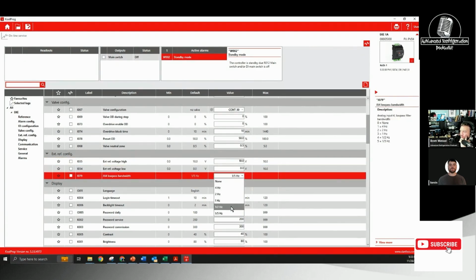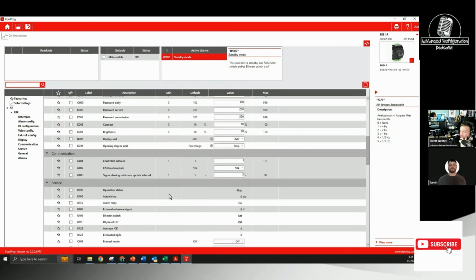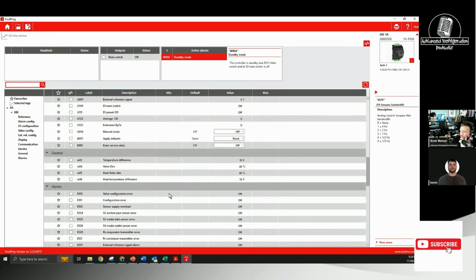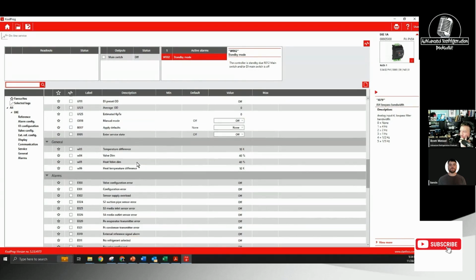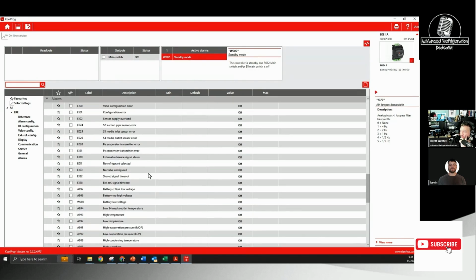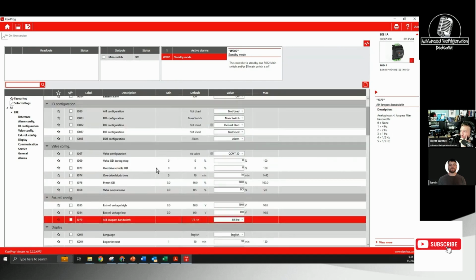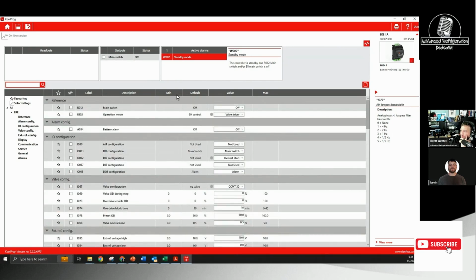Then you give the thing a slap and a power cycle, and it's good to go. Really, that easy? Temperature difference, valve down—it has all this other stuff, but for the most part you're using it to drive that valve, and that's really it. Yep, that's it. It literally gets 10 volts, valve's full open, gets 0 volts, valve's full closed, switch gets turned off, valve shuts.